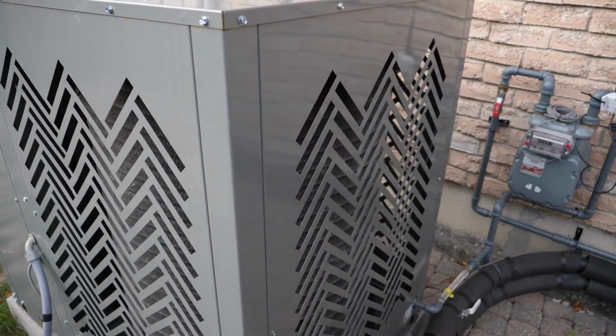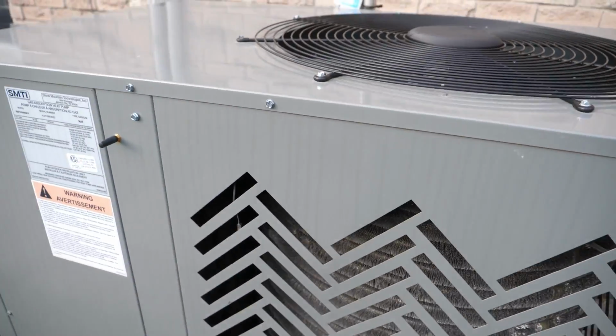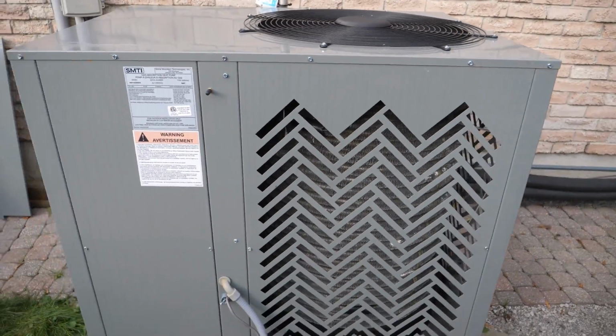Yeah, it'd be an easy repair, and I will tell you this. We obviously want the lines to be well protected and secured. If somebody does happen to bump into one and you spring a minor leak, the air handler downstairs has a reserve tank that's going to continue to make up that volume until it gets to a point where it's got to be fixed. Then you're going to get an air signal that's going to shut down, and the contractor will know. But by the time that happens, between the contractor monitoring it and our monitoring it, we'll have a pretty good idea what's going on. Well, the reality is, as soon as they hit this line, we're no longer moving fluid. The unit is going to see a high temperature event. It's going to lock itself out on high pressure anyways. It'll protect everything. The homeowner will get an alert. They'll call, the contractor will come out and they'll fix it.